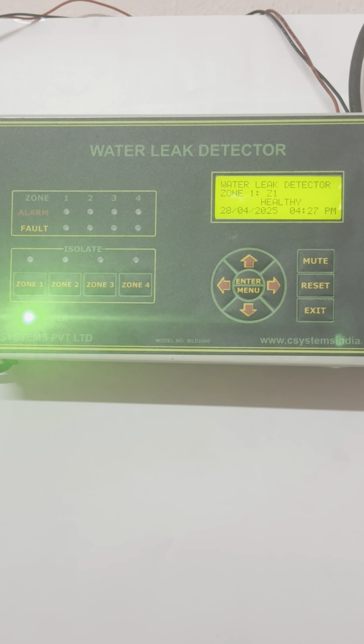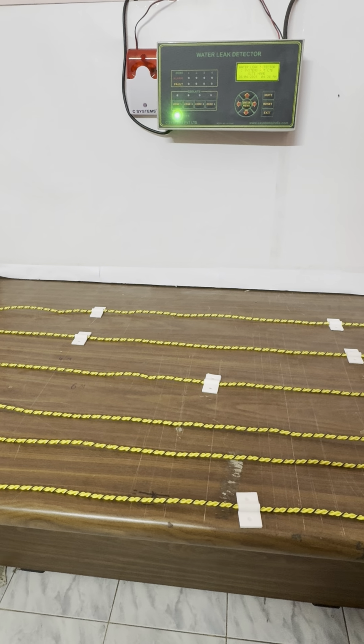So now the sensor cable is already connected. I will show you the sensor cable which is laid for demonstration purposes. You can see the sensor cable being laid on a demonstration table, and the fixing clip is used to firmly fix the sensor cable such that it will not lift from the floor. In this way, you have to install the sensor cable in the critical rooms. If the floor is tile, you can use double-sided tape. If the floor is concrete, then you have to nail the fixing clip in order to fix it firmly.